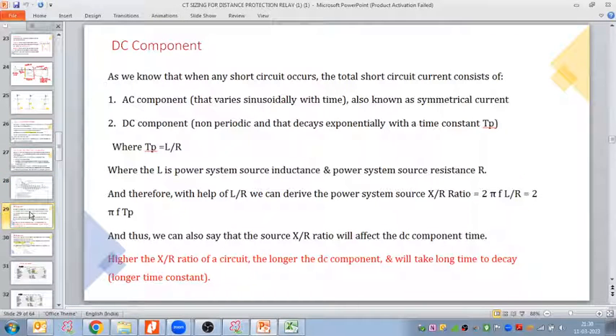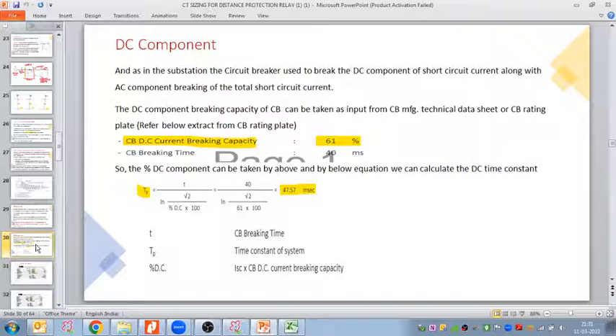So this we have seen yesterday, the nature of fault current. With the nature of fault current, we are trying to calculate the source resistance and the source reactance. The DC component decaying rate depends on the X/R ratio. Again, all this we discussed yesterday. Here we calculated the time constant required to decay the DC component when a fault happens. When the fault happens, initially the fault has the AC component and the DC component, and the DC component takes 47.57 millisecond to decay.